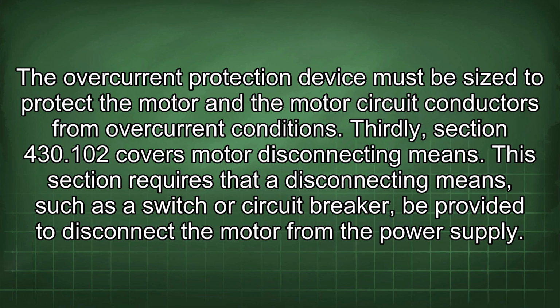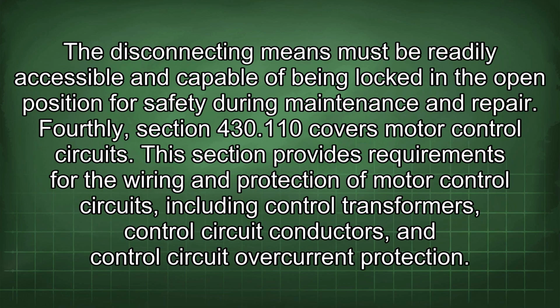Thirdly, Section 430.102 covers motor disconnecting means. This section requires that a disconnecting means, such as a switch or circuit breaker, be provided to disconnect the motor from the power supply. The disconnecting means must be readily accessible and capable of being locked in the open position for safety during maintenance and repair.